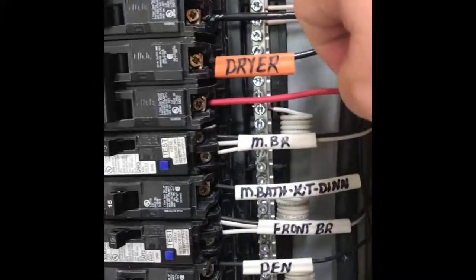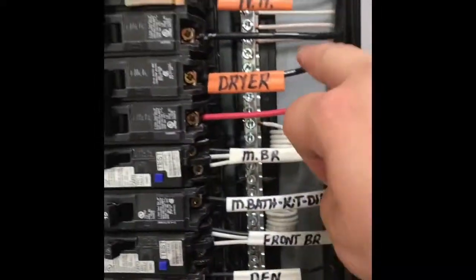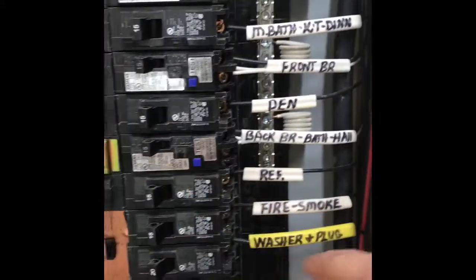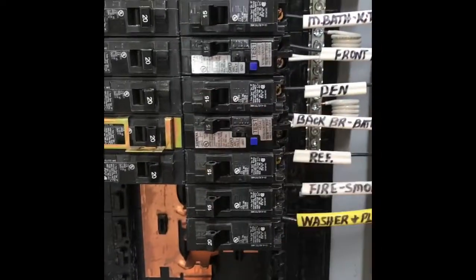The home inspector's also going to go through and make sure all of the branch wire circuits are compatible with whatever breaker they're set on, depending on gauge. Every single wire will need a different gauge. You know, for 15 amp, you're going to want 14 gauge wire minimum. Then it goes up from there. Then we're going to make sure the service entrance is correct.